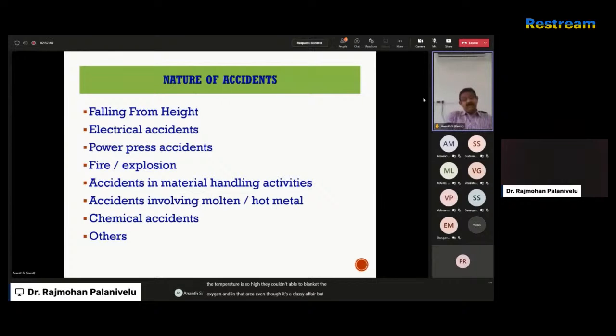One thing I infer from that fire accident is that the pressure at which the water was applied is very important. In factories we generally have sufficient fire hydrants, pumps and pipelines, but we have to check whether the pressure pump has sufficient head. You have to check the nameplate and verify whether the pressure at which water is applied is adequate. If not, we may just be pouring water without extinguishing the fire, so we have to be very careful.